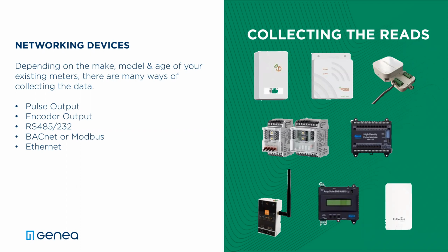Very, very wide range. Depending on the exact brand you go for and the local labor rates, it can vary quite a bit. A typical E-Mon D-Mon meter is about $1,000, 1,500 to $2,000 installed. A dent meter is somewhat cheaper, but it depends on the size of the CTs, any other options you pick with the E-Mon D-Mons, and local labor rate is the biggest factor—do you have to do a complete shutdown, et cetera. But you should be able to get a single three-phase meter installed for 1,500 to $2,000 normally.